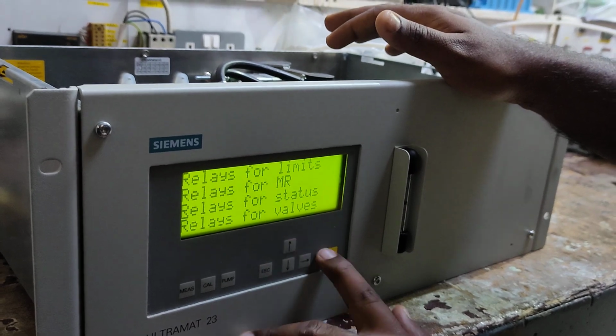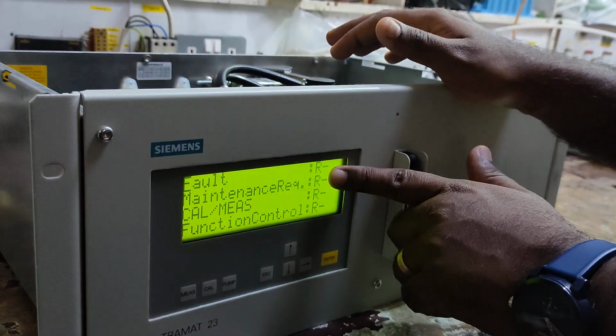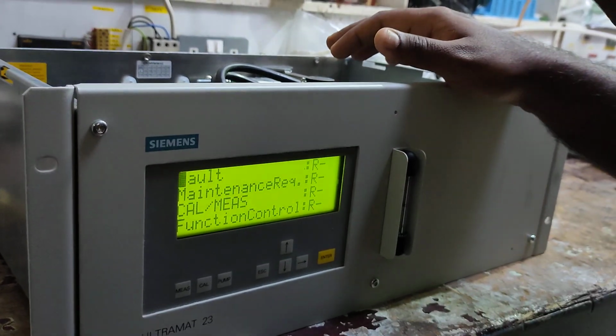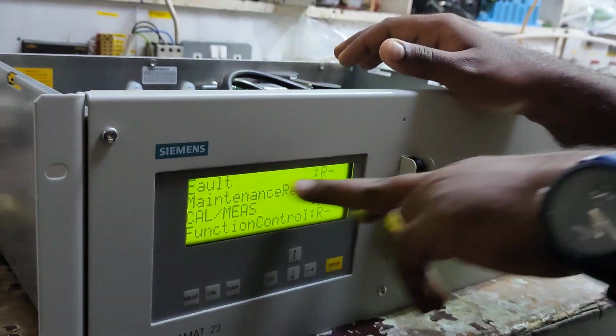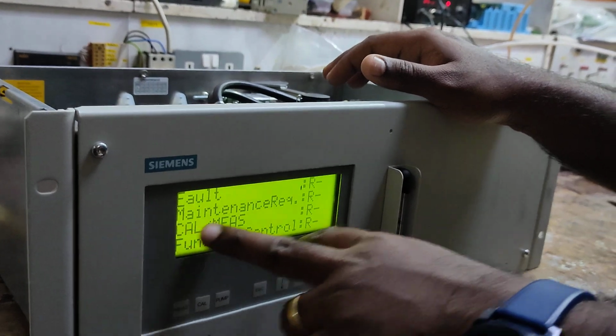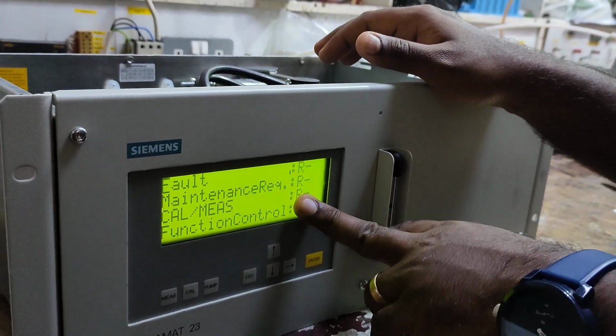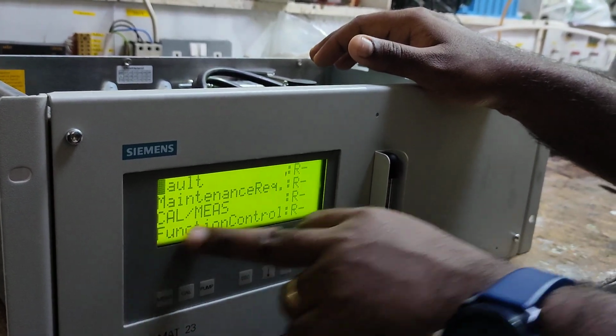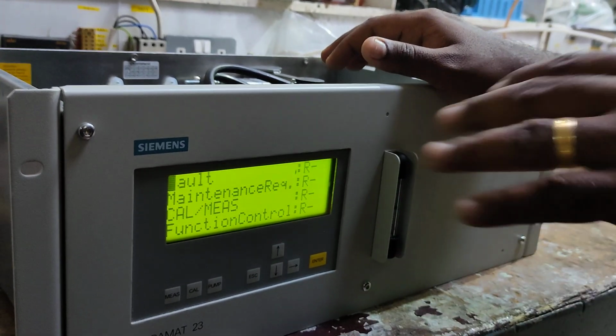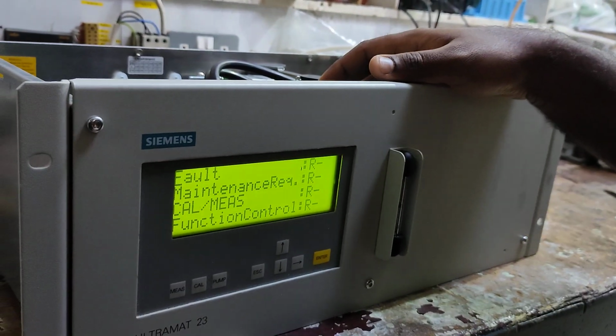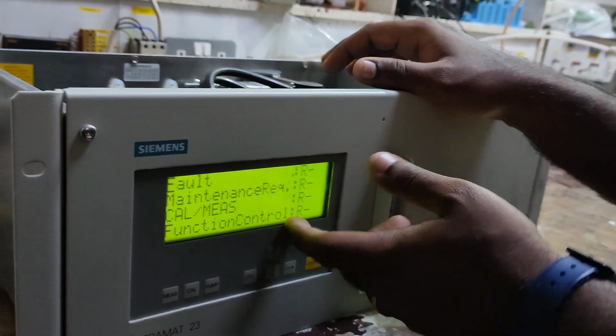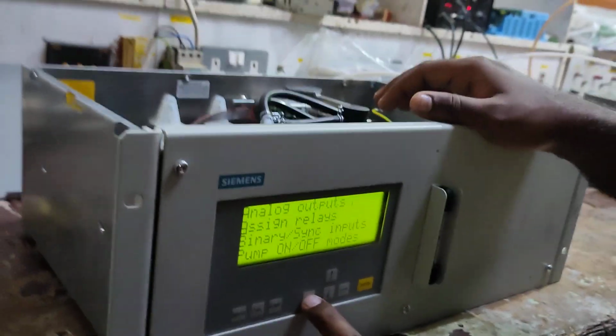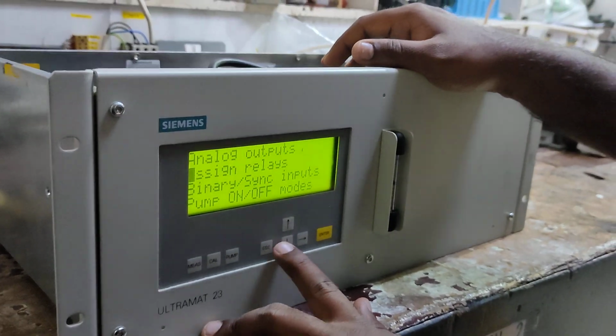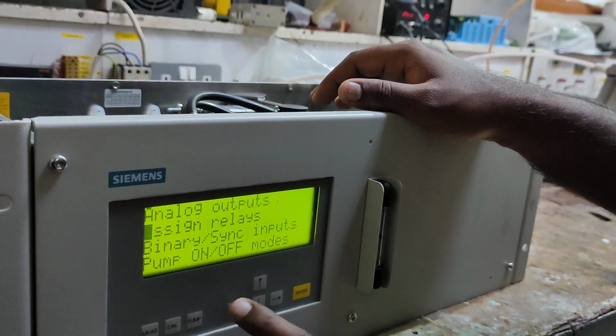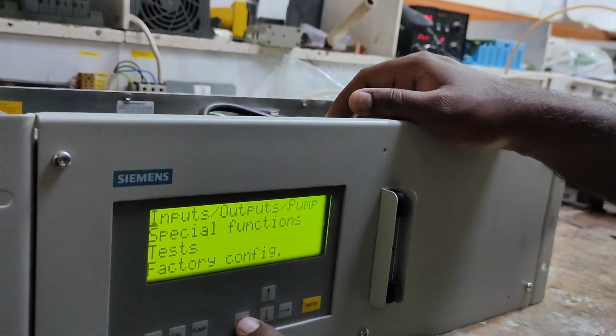Similarly, for status, if you have a common fault, you can configure the relay. Which relay should give common fault? If it is relay 1, you can connect that cable which goes to the DCS as a common fault. Maintenance request, and whether the system is in calibration mode or in measure mode, or function control. If someone has come and gone inside the function, and you want that to be reported in the DCS, you can select that also. We can see at what time something happened. Okay, so these two things are very important, analog output and this.